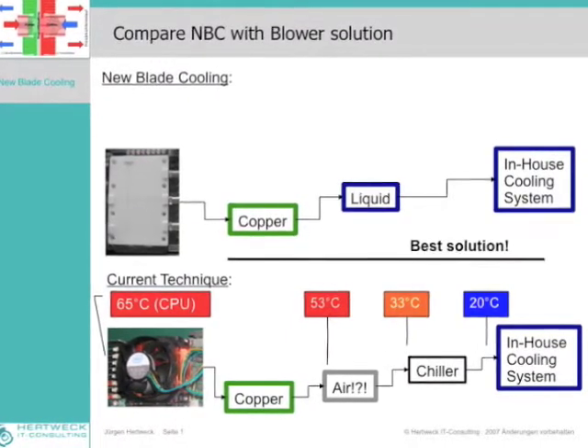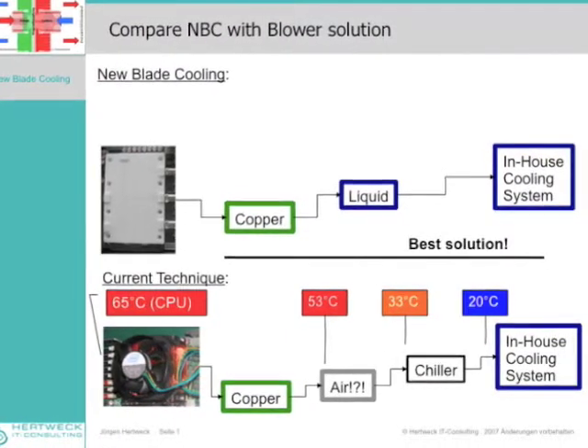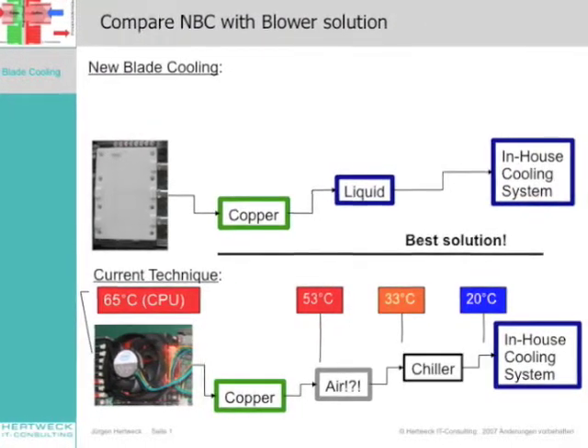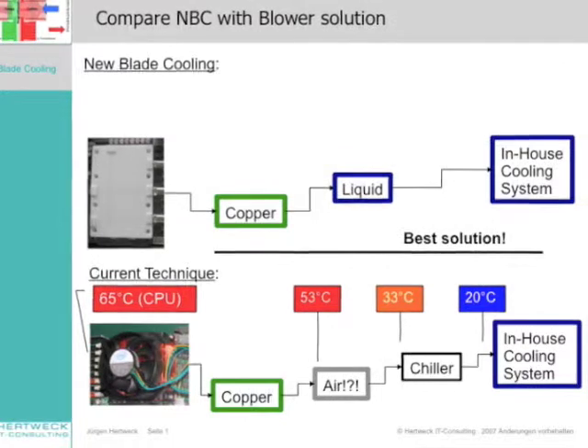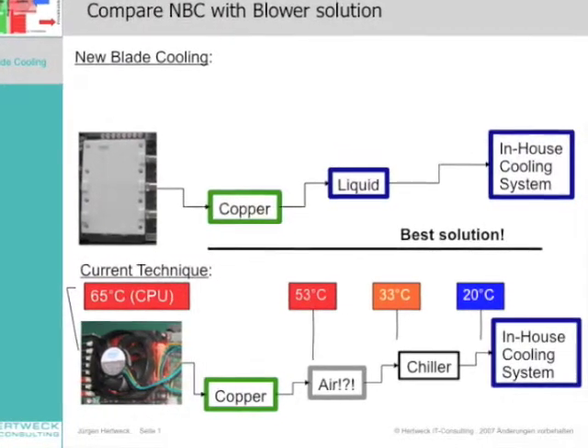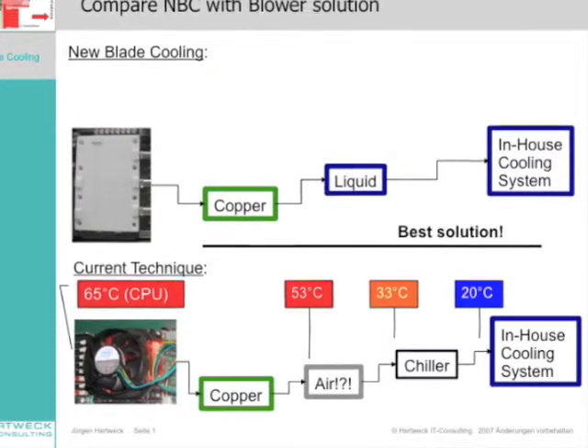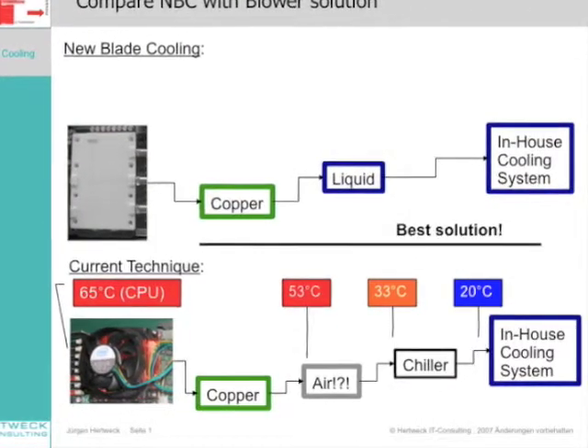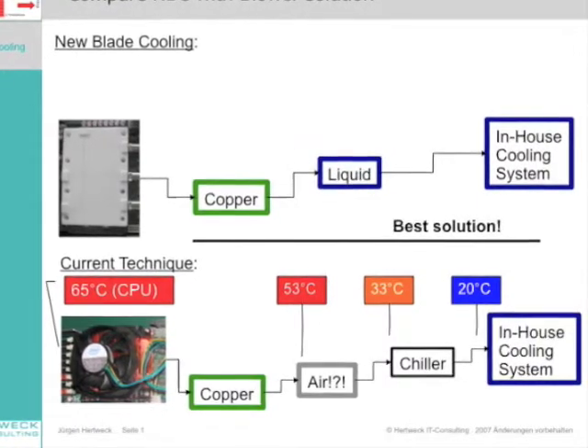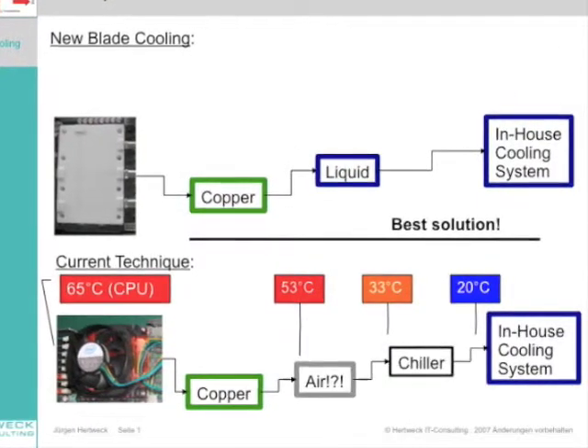Normally, the blade server has an air out streaming with a temperature of 53 degrees Celsius and this is cooled down by the water air chiller to 33 degrees Celsius before the air is streaming inside the server again. To achieve these values, the water air chiller has to be supplied with a water temperature round about 20 degrees.